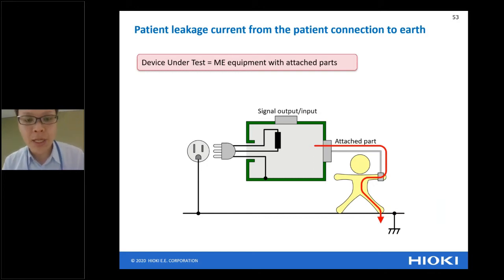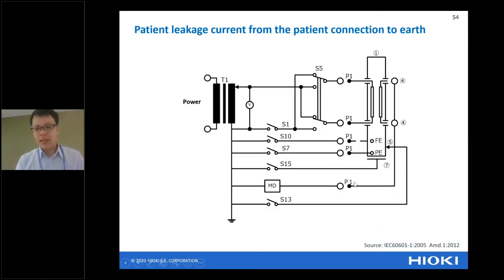Okay, finally, patient leakage current from the patient connection to earth. The device under test is an ME equipment with an applied part. The applied part here is actually connected to the human. So in that case, how much is the leakage current? These are the standard figures. This is the measurement part. From here, here is the applied part, and it connects to the MD. In that case, you can measure patient leakage current from the patient connection to earth.